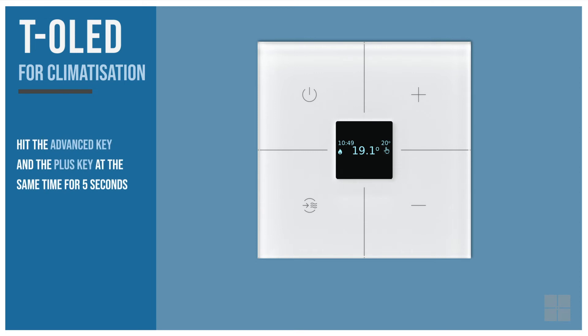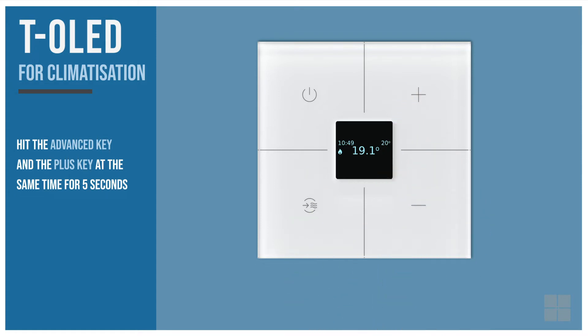To do it, hit the advanced key and the plus key at the same time for 5 seconds. If you touch both keys briefly, the touch panel moves to thermostat mode temporarily and comes back to automation mode after 10 seconds of inactivity.